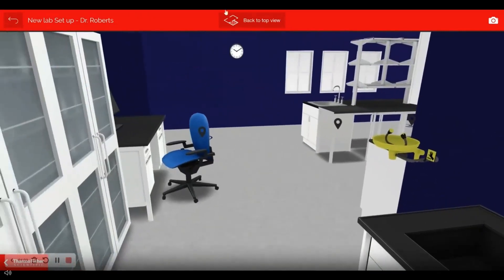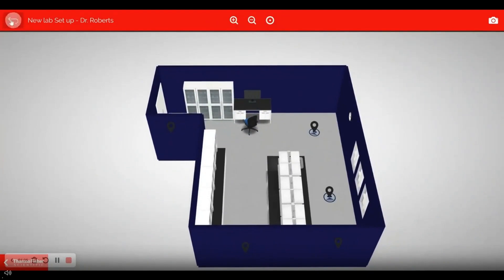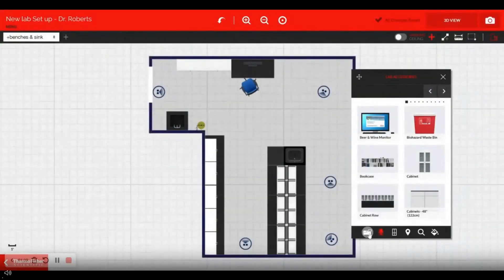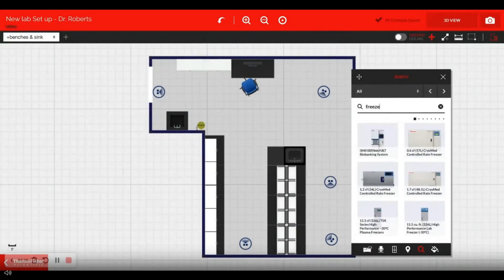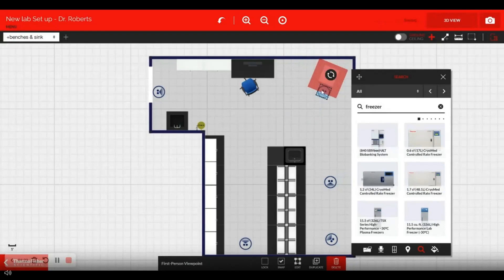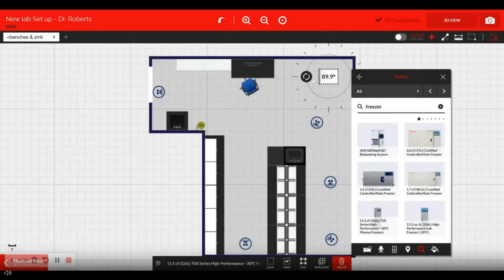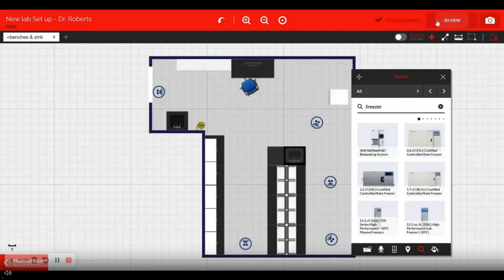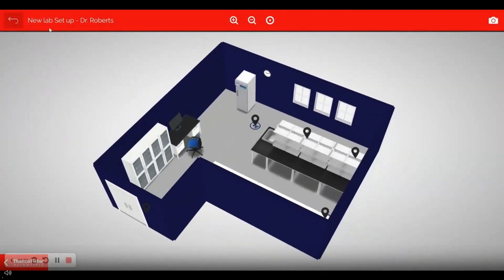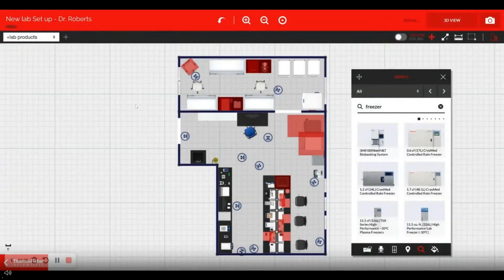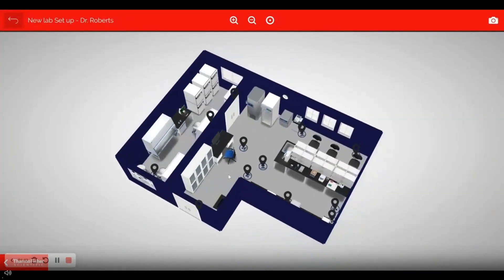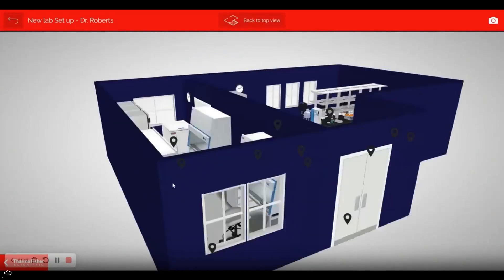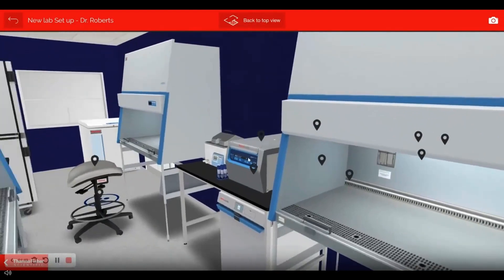This is how we've positioned the benches that were already in place and can't be moved, so we wanted to start from that spot. Next, we're going to add the equipment. This is the equipment list built with your Thermo Fisher Scientific specialists or account rep teams, and they can actually help you position these. You're going to see a little halo around the products — this is really a guideline on the required clearance, which is a nice feature so you're not positioning things where you can't open doors. This is an example of the lab where we've added all of the different elements. You can then land yourself on the ground, have a look around, and check if the space makes sense — all on your computer in 3D.